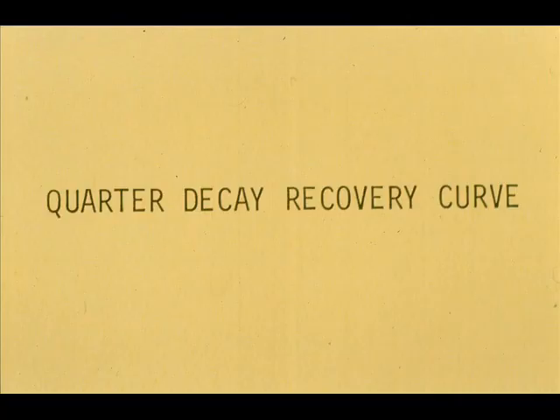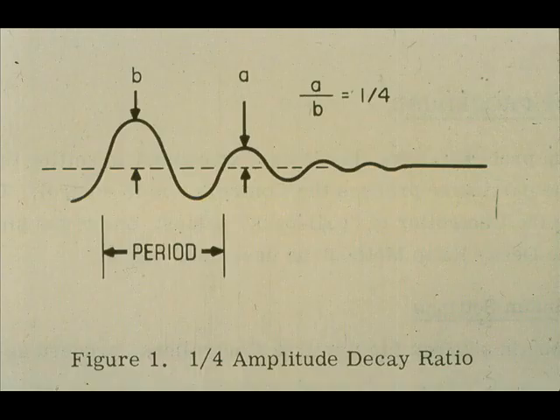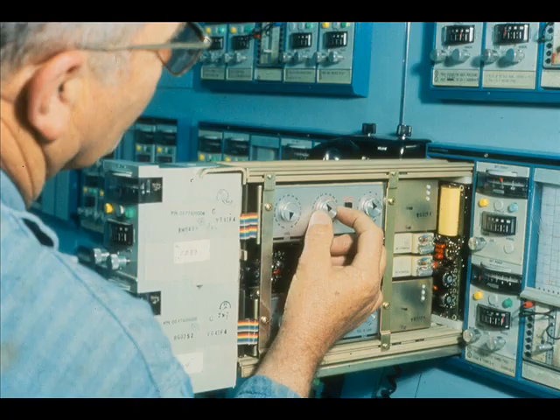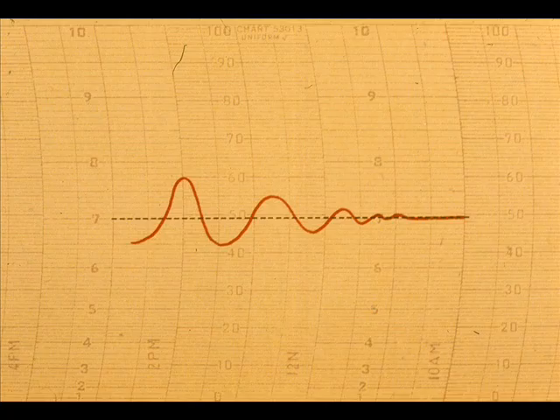A quarter decay recovery curve is generally considered to be the optimum. Quarter decay means the magnitude of each cycle after the first one is one-fourth as large as the preceding one. Our goal will be to tune the controller to get this response from the process.